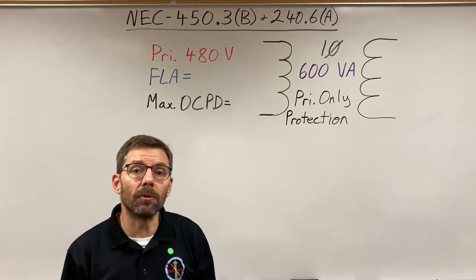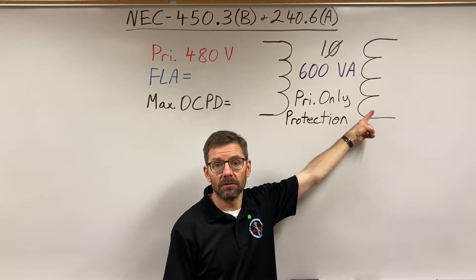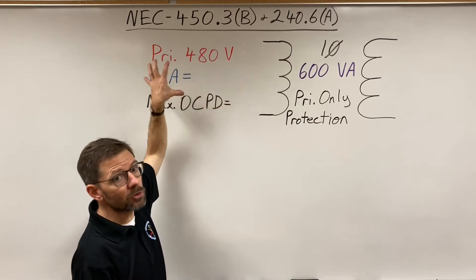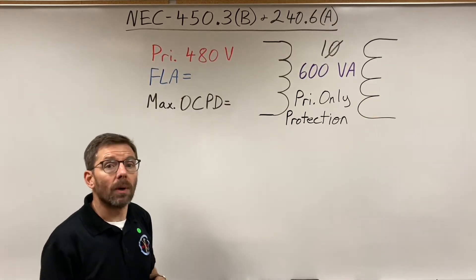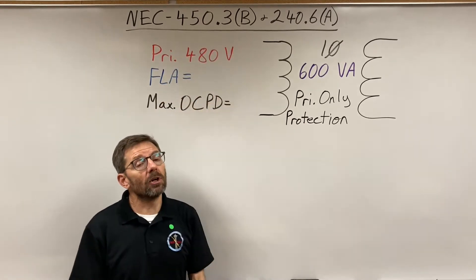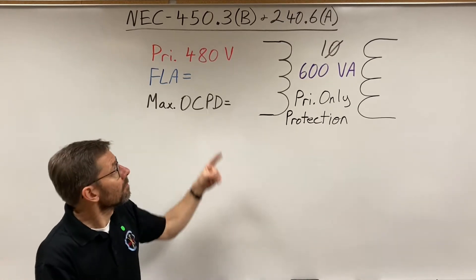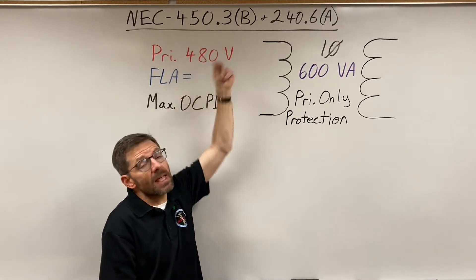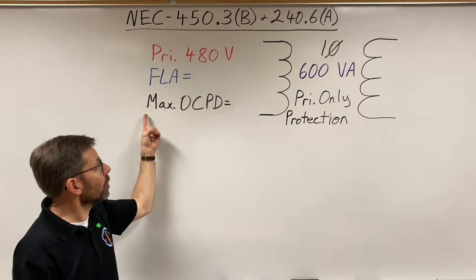In this video we're looking at transformer protection — protecting the windings of a transformer from overcurrent. The focus is the primary only method: a circuit breaker or fuse on the primary that protects both sets of windings. We turn first to Article 450.3b, overcurrent protection of transformers 1000 volts and less, which directs us to the table of the same number. Make sure you're on Table B, 1000 volts or less.